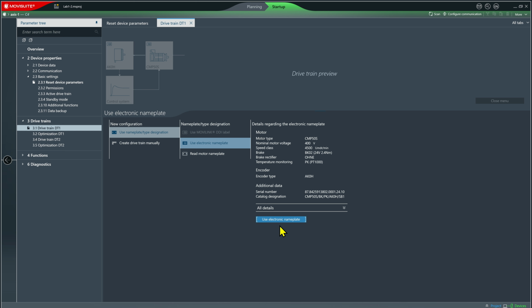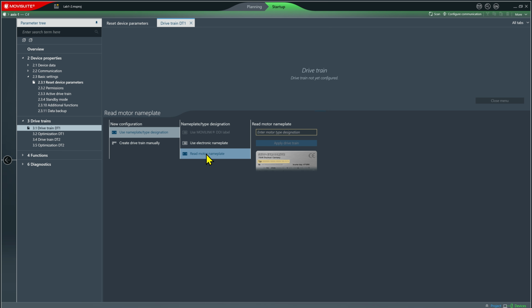I could, of course, just click the button, use electronic nameplate, to make a quick and easy commissioning. But what I want to demonstrate here is how you commission a motor that does not include an electronic nameplate. We're going to do this the manual way. So I'm going to click Read Motor Nameplate instead, which will ignore my electronic nameplate. And now I've got to type in my motor's nomenclature right here. Now, to get the nomenclature, you need to look at your motor's physical nameplate.